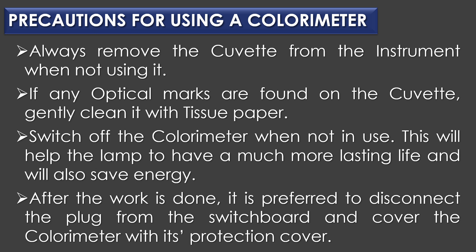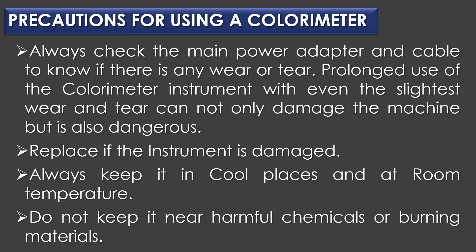Precautions for using a colorimeter: Always remove the cuvette from the instrument when not in use. If any optical marks are found on the cuvette, gently clean it with tissue paper. Switch off the colorimeter when not in use to help extend its life and save energy. After work is done, disconnect the plug from the switchboard and cover the colorimeter with its protection cover. Make it a habit to check the main power adapter and cable for any wear or tear, as prolonged use with even slight wear and tear can damage the machine and is dangerous. Replace the instrument if damaged. Always keep the instrument in cool places at room temperature, and do not keep the colorimeter near harmful chemicals or burning materials.